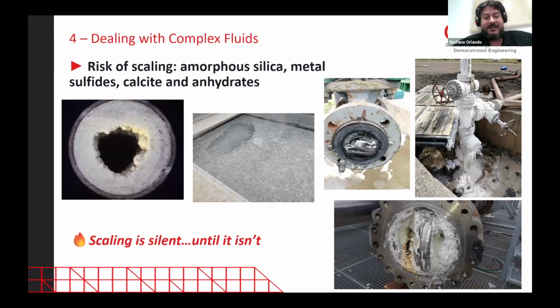The second picture is a weir box, equipment usually coupled with the atmospheric flash tank used for startup and emergency. Here there was a brine high in silica content, and because of the heat and evaporation of the brine in this weir box, the water crystallized at the surface like glass. That is actually silica, that is glass. The phenomenon was amazing - one morning I went there and said, 'what's there, who put a panel of glass on top of here?' And actually it was just the silica crystallizing.